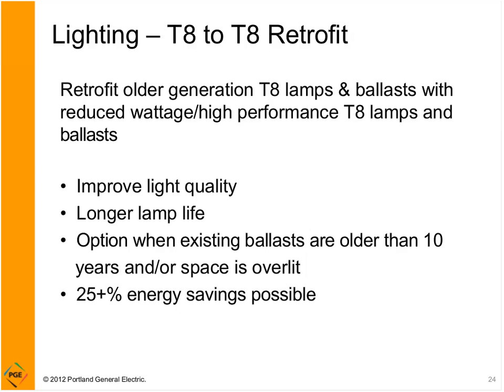One choice is to spot replace the ballast and lamps as they go out, knowing that this is going to be kind of an ongoing issue. There aren't any incentives to do anything like this. You're probably going to end up with the same light level and not much energy savings. But if you looked at it as a project, you can actually get some money back to retrofit an entire lighting system with newer generation T8s and possibly reduced wattage and so on. It might be reducing the number of lamps or changing the ballast factor of the ballast you're using.